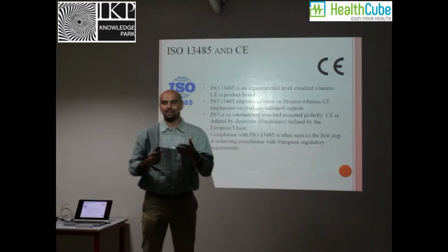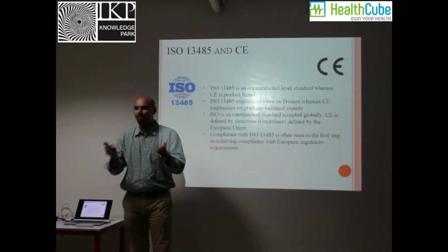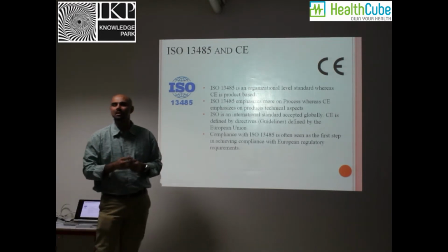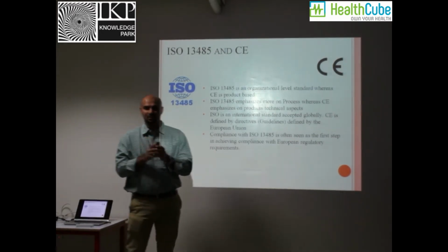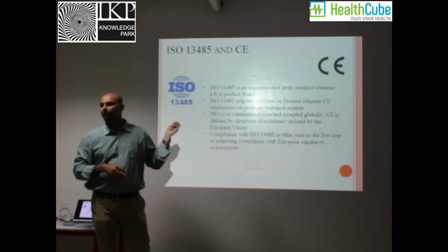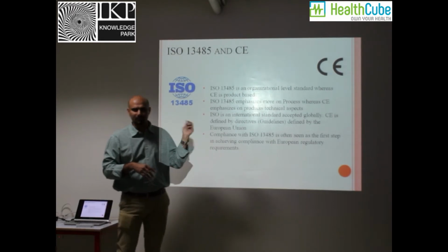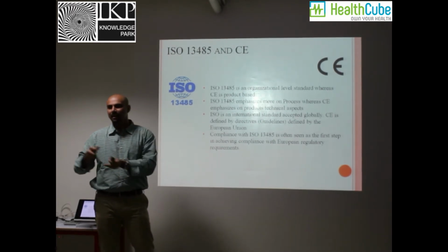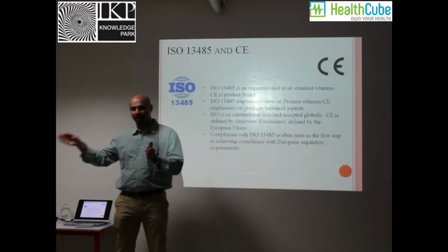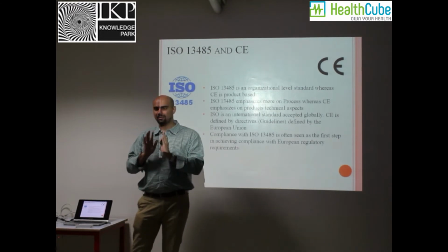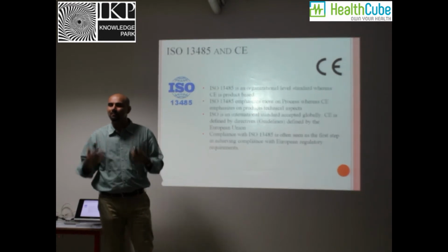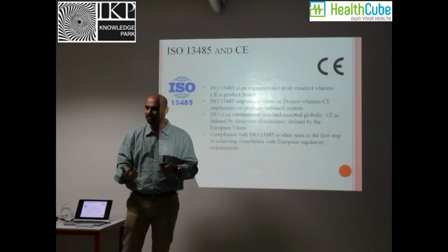And hence I keep saying ISO 13485 is your basic formation, and it depends on how closely you are meeting the ISO 13485 requirements. The good thing is the 2016 version has actually tried to put itself in line with US FDA and the new regulations that are coming up for Europe as well, MDR and IVDR. I spoke about that in my previous session, but MDR and IVDR is something that's going to come up. Currently we have MDD and IVDD. It's going to be replaced by MDR and IVDR. And the 2016 version is very much in parallel with US FDA and MDR itself, right? So that helps us in complying with these regulatory requirements as well.